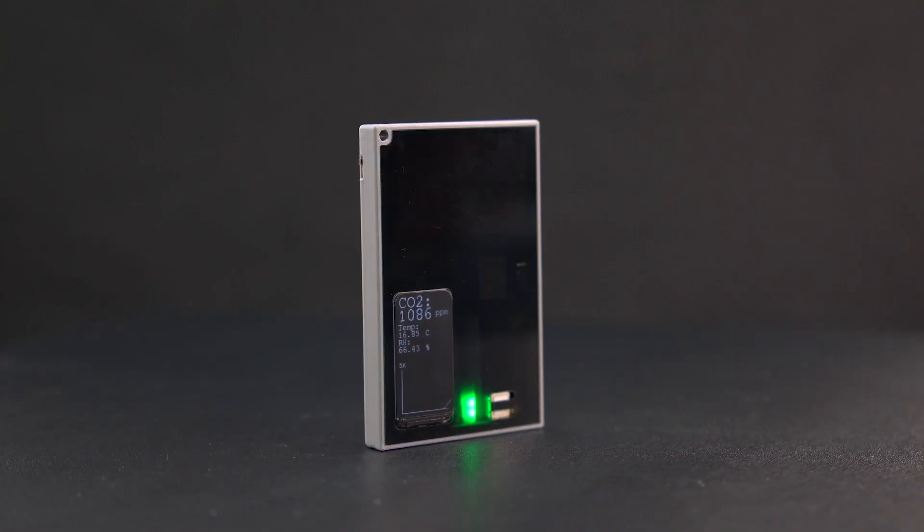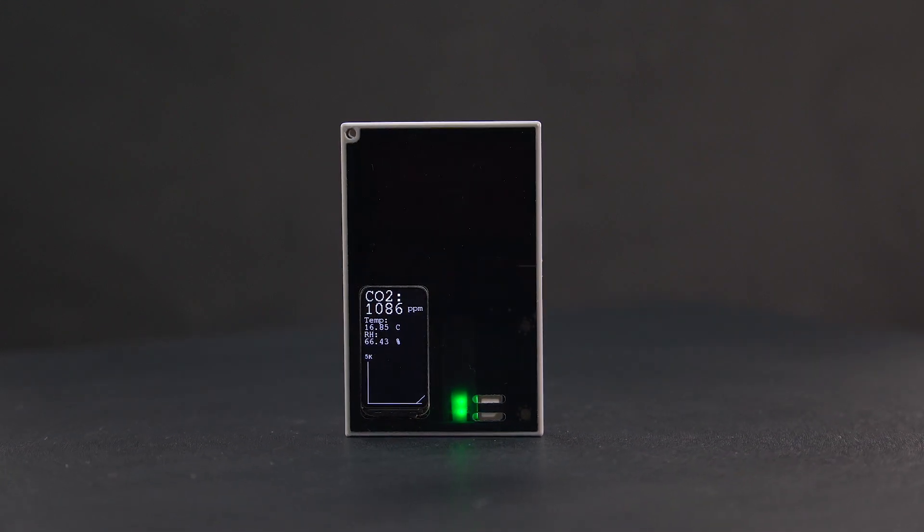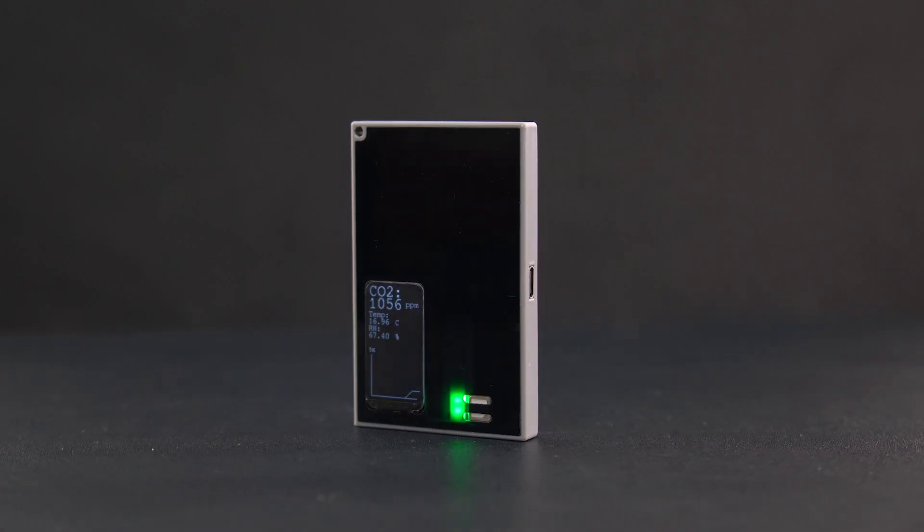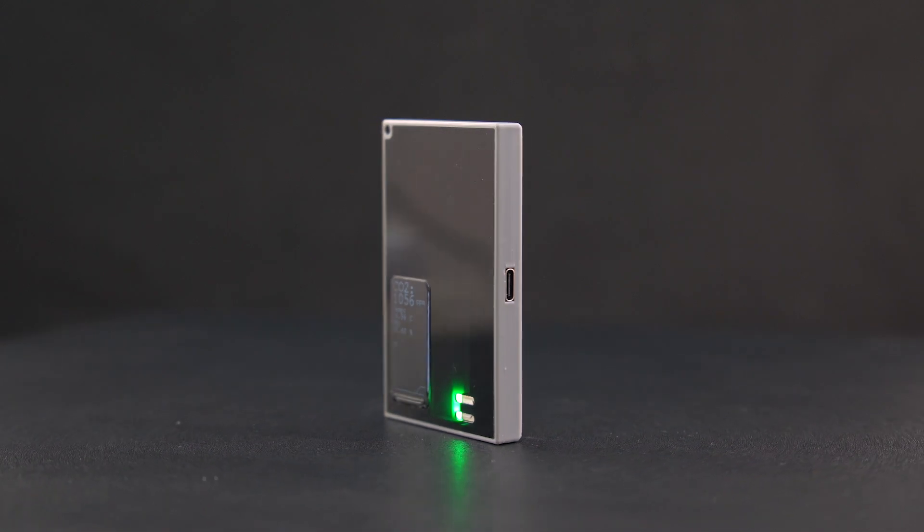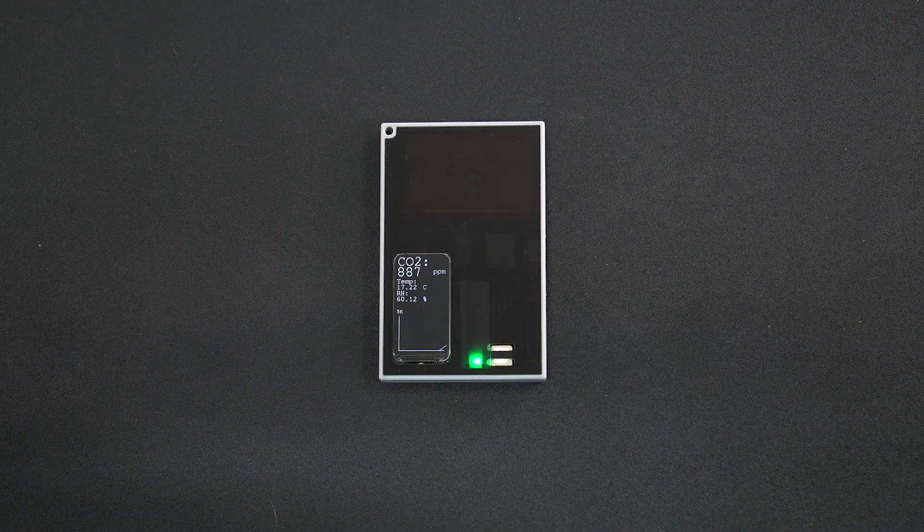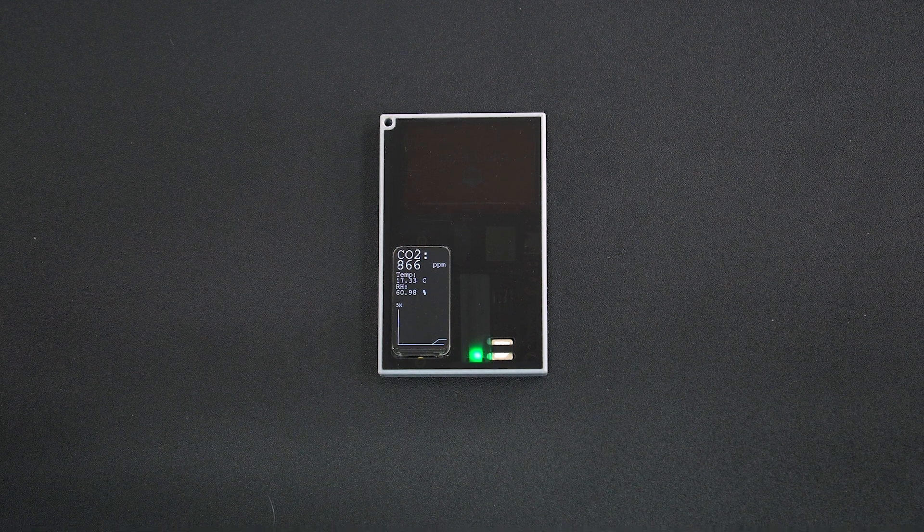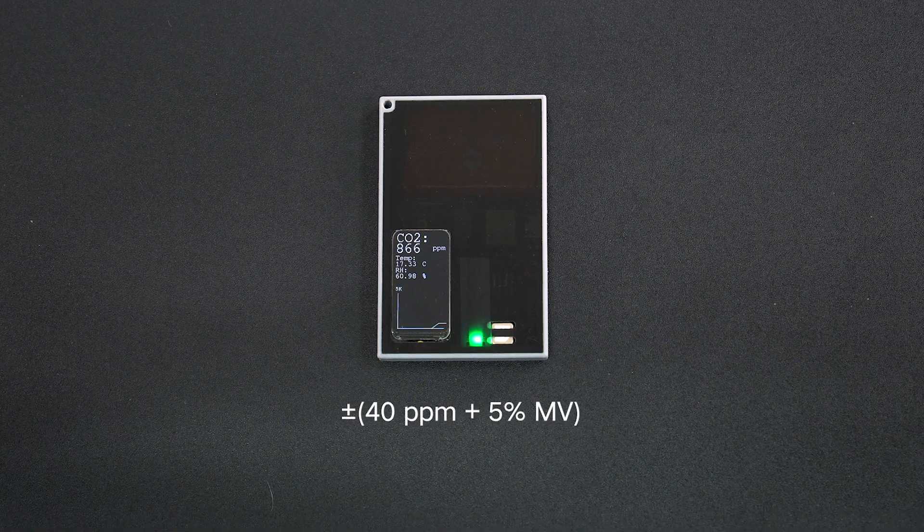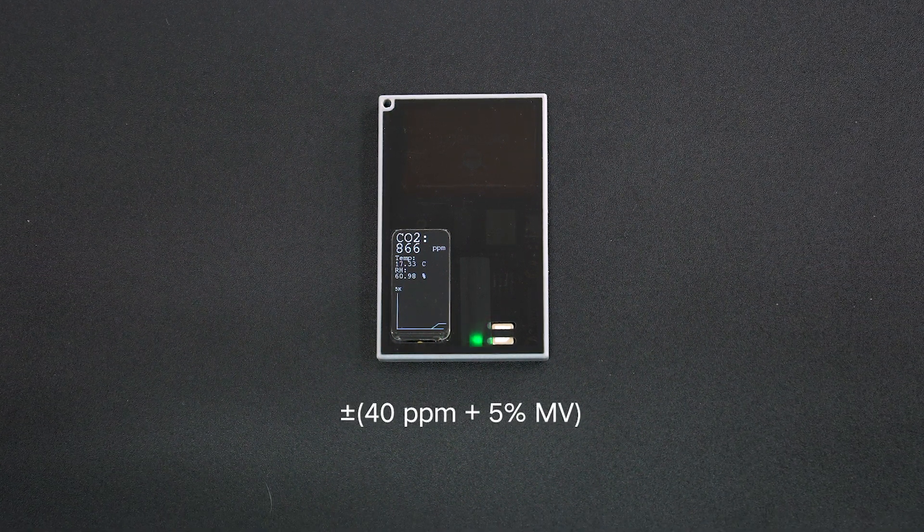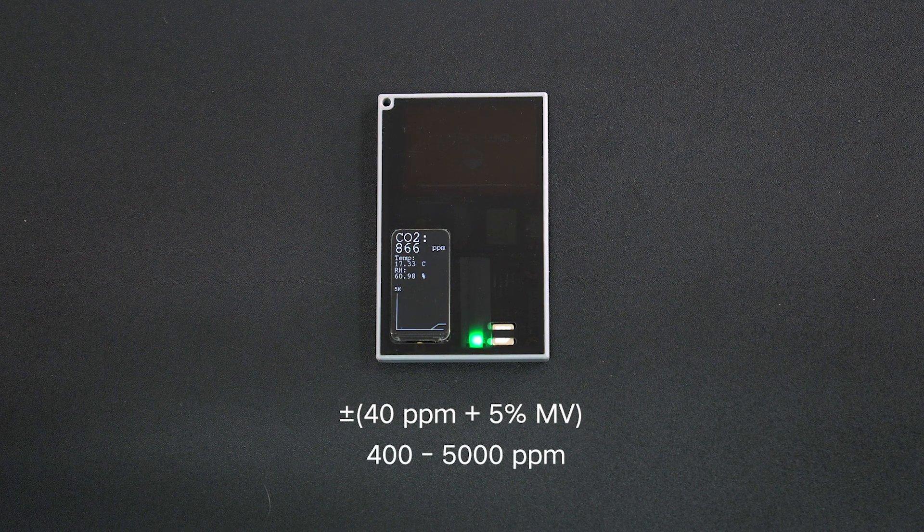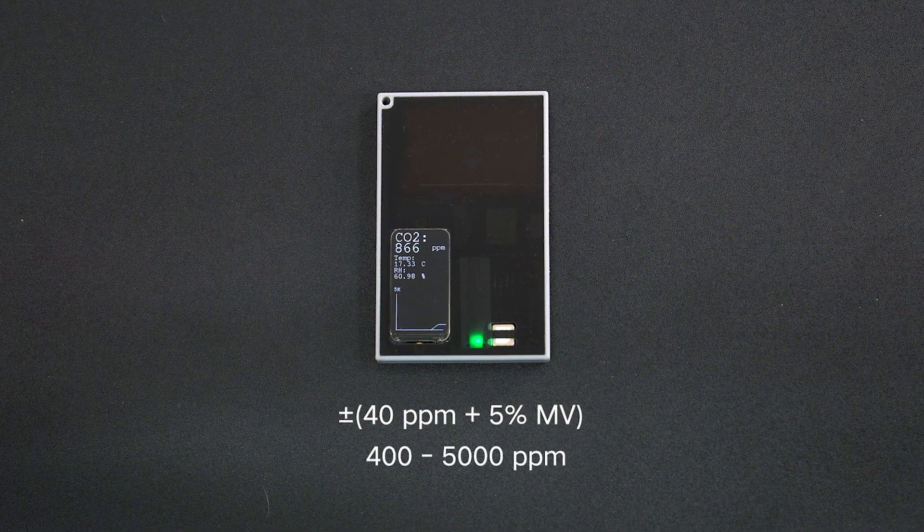The innovative use of microphones for carbon dioxide detection allows for a significant reduction in the required volume of the optical chamber in the infrared absorption method. This small photoacoustic carbon dioxide sensor provides an accuracy of ±40 ppm plus 5% MV in the 400 to 5000 ppm measuring range.